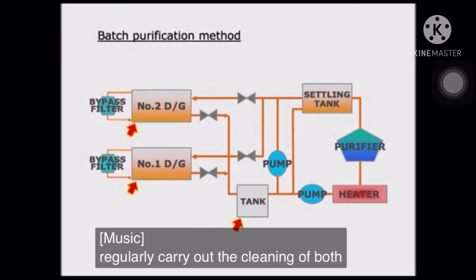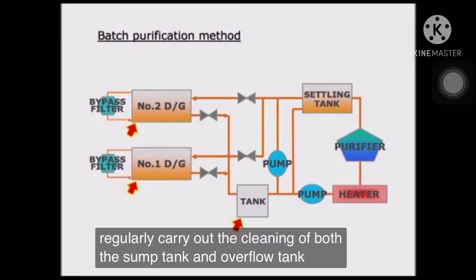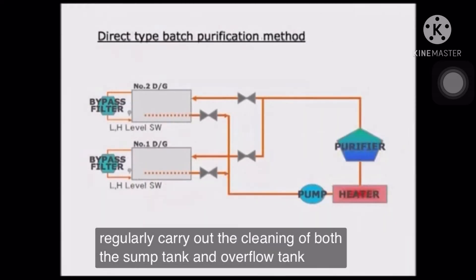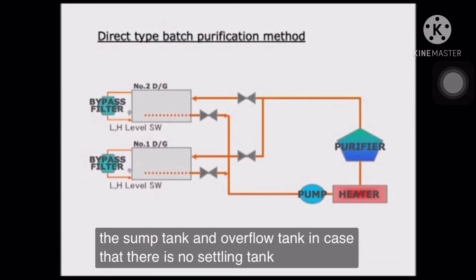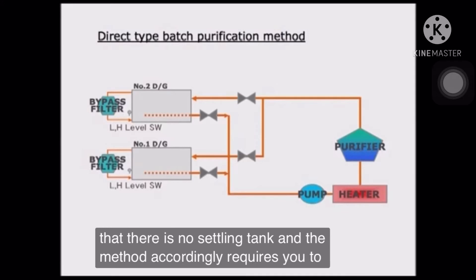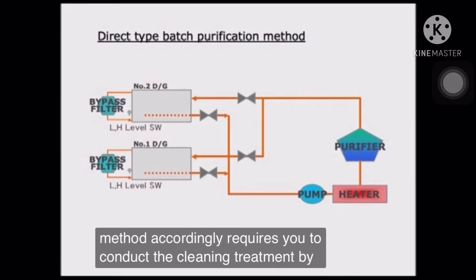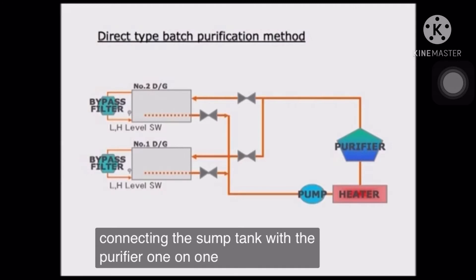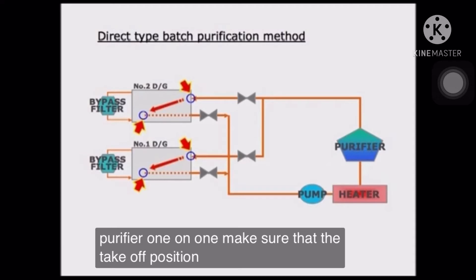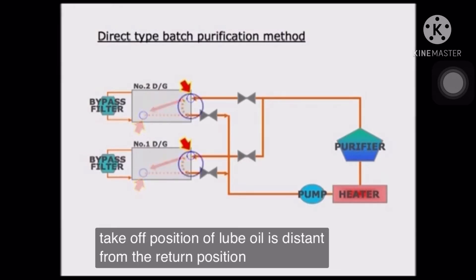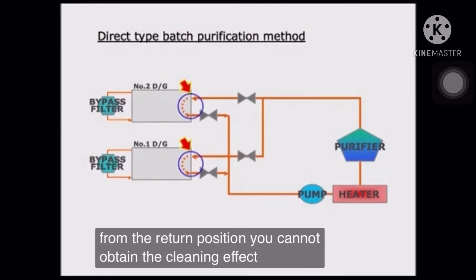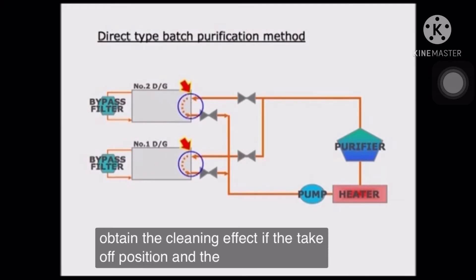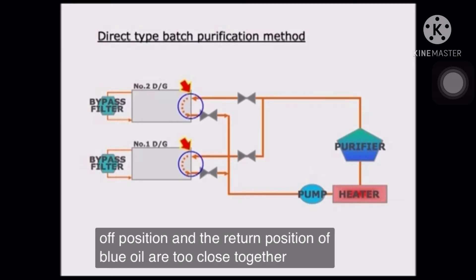Regularly carry out the cleaning of both the sump tank and overflow tank. In case there is no settling tank, the method accordingly requires you to conduct the cleaning treatment by connecting the sump tank with the purifier. Make sure that the take-off position of lube oil is distant from the return position. You cannot obtain the cleaning effect if the take-off position and the return position of lube oil are too close together.